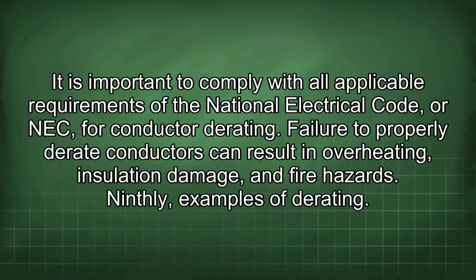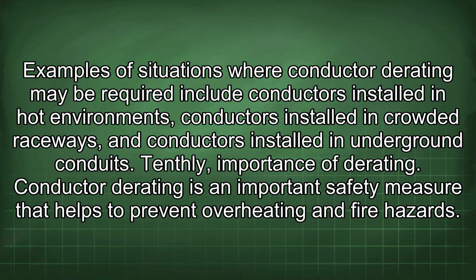It is important to comply with all applicable requirements of the National Electrical Code, or NEC, for conductor derating. Failure to properly derate conductors can result in overheating, insulation damage, and fire hazards. Ninthly, examples of derating. Examples of situations where conductor derating may be required include conductors installed in hot environments, conductors installed in crowded raceways, and conductors installed in underground conduits.